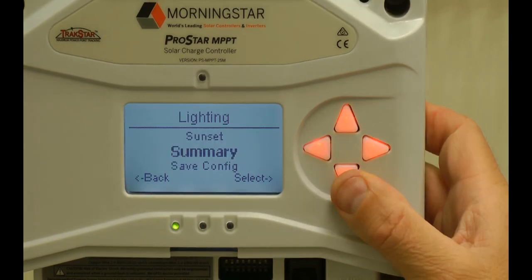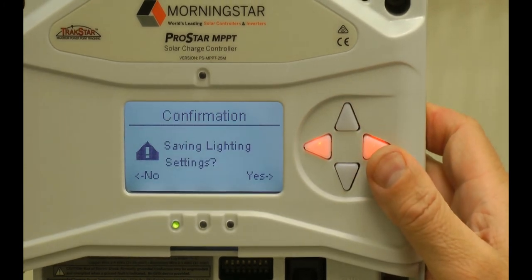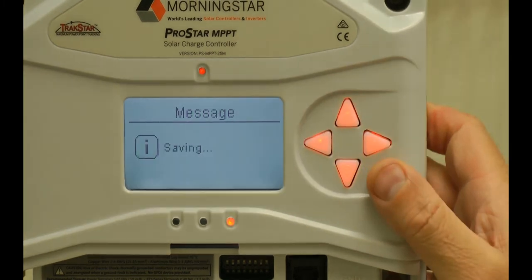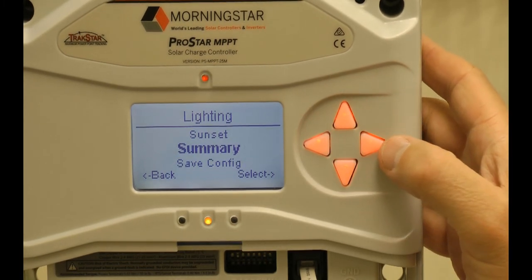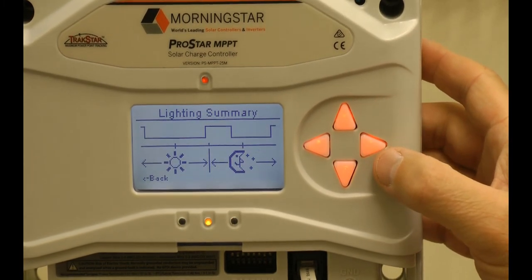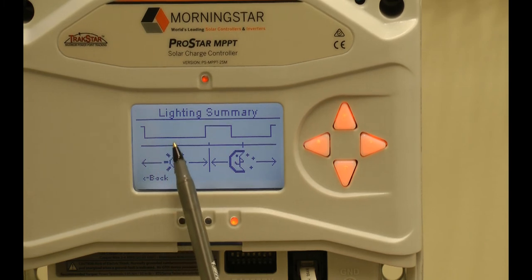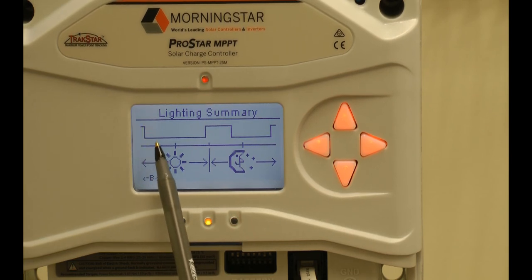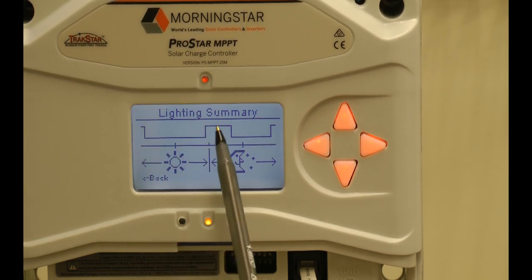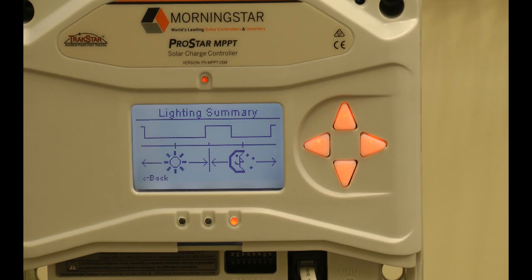We want to go down and save our configuration. Select save config and hit the right arrow to select, then confirm by hitting the right arrow again for yes — and it has saved our programming. At this point, you can go up and look at your summary. As you can see, if there were no lighting timers it would just be a straight flat bar. But what we can see here is that in the morning the lights are on, and then they're on again as evening hits. This is just a rough estimation of what's going on with the timers, but it is a method to check that your programming took effect.